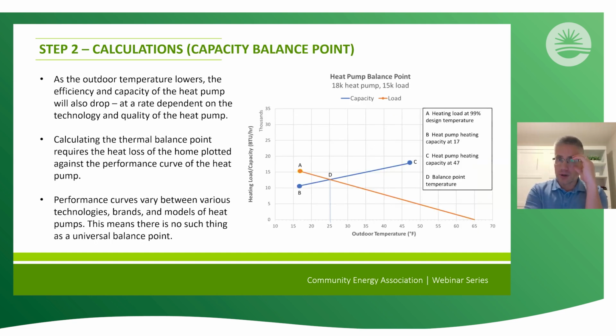We talked about this a little bit earlier, but the second piece of calculation that's needed is what's called the capacity balance point calculation. There are kind of two things that go into determining this. One is the heat loss of the house, which is shown on this orange line that shows the increasing capacity that's needed as it gets colder. And then with heat pumps, their capacity lowers as it gets colder. The intersection of those two lines is what's called the balance point. So this space between them, as we were talking about earlier, is the supplemental heating that you're going to need, where the heat pump can only deliver this amount, but your house actually needs that amount, right?